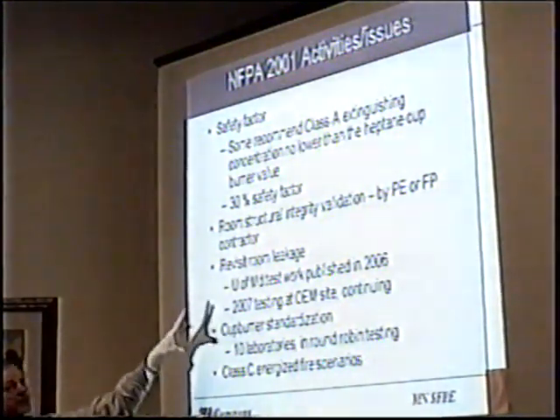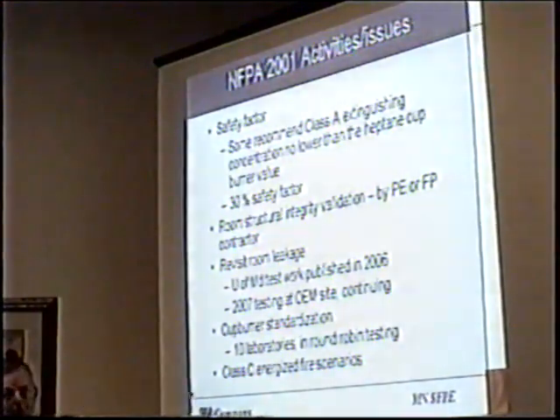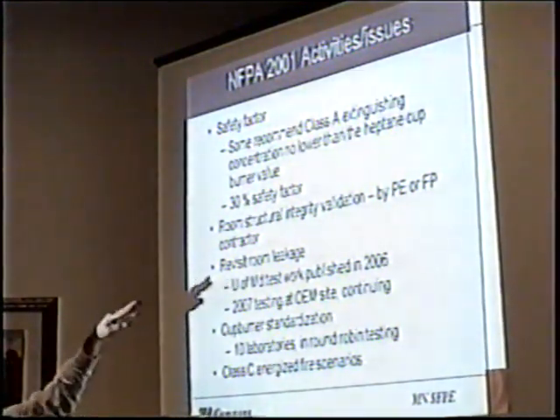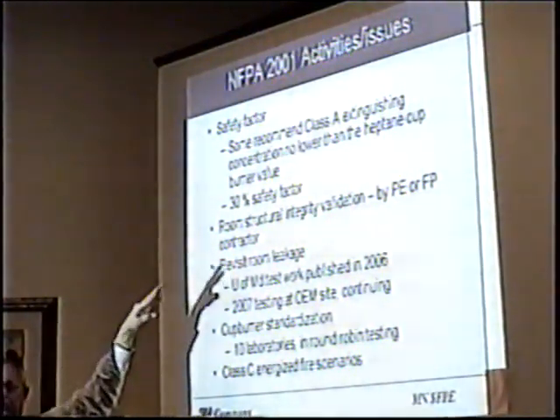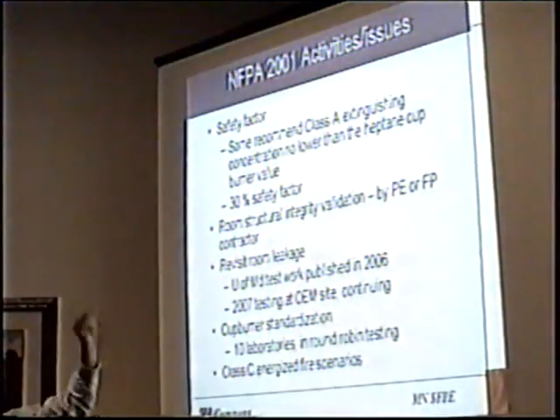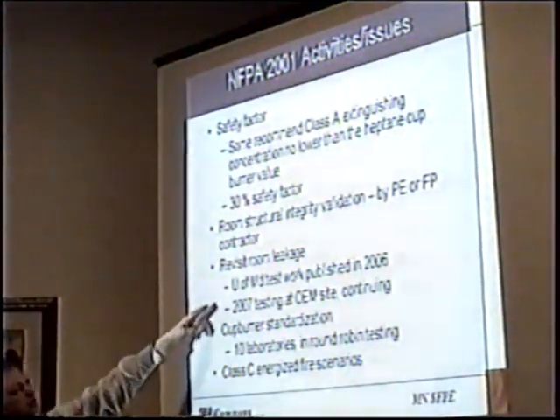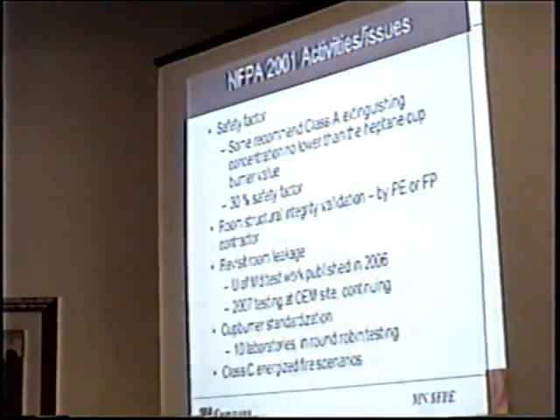This room leakage, that's basically why Todd's doing the work that he's doing. There's a lot of work going on to provide data, to give guidance for that, and to put what I believe is where this should go back to, which is a professional engineer. Revisit the room leakage. There's been testing done at the University of Maryland, and also, at 2007 testing, the OEM site is continuing. There's some work that was done last year, and also going to be this summer as well, actually in July, at Fike Corporation. Cup burner standardization, this is kind of a hobby of the standard. We do this every cycle for the last 15 years now. And we debate cup burners, so I think we might actually have it this year now, we have round robin testing. And then continue with the energized fire scenarios.